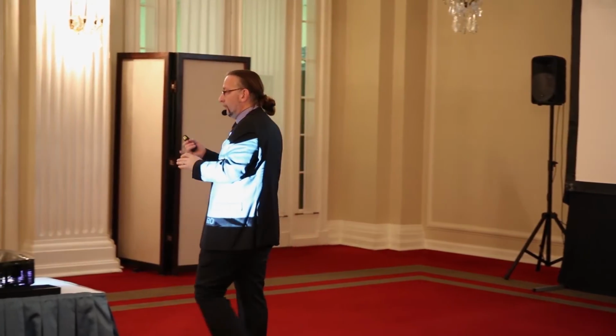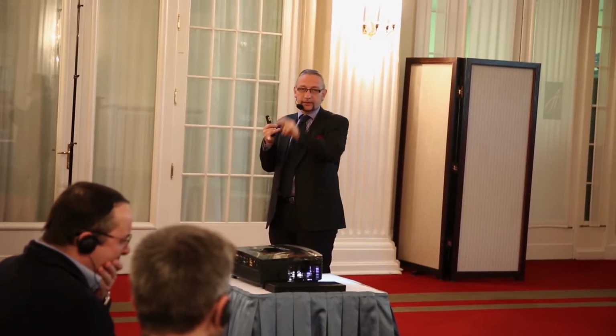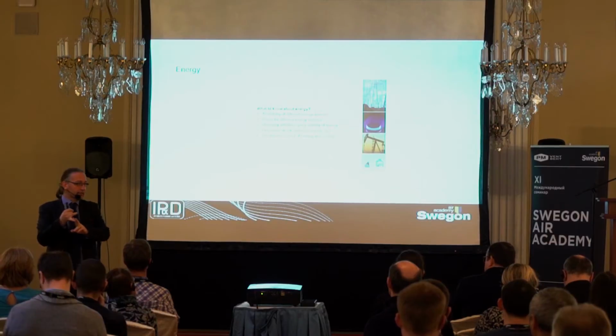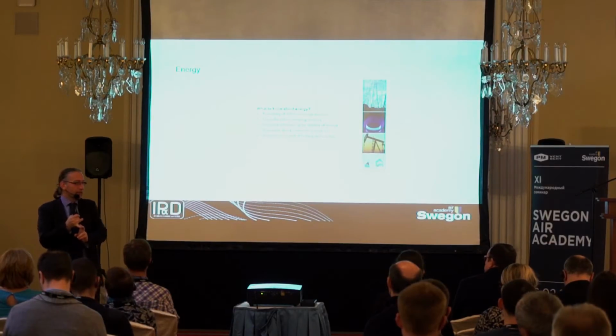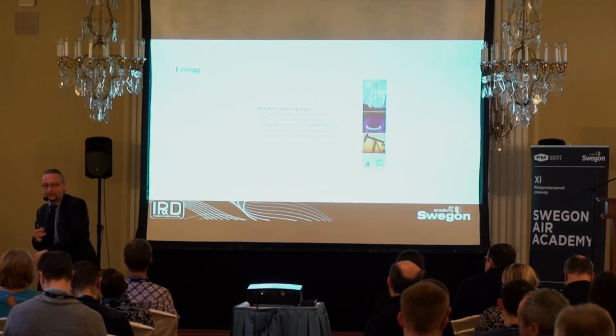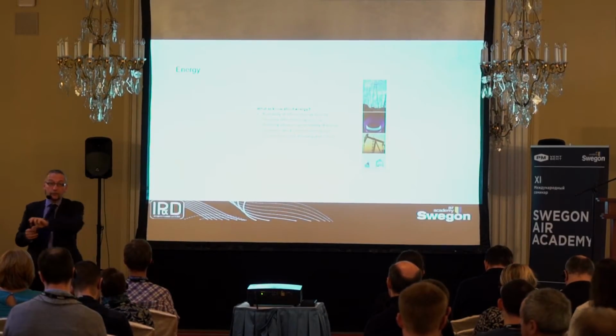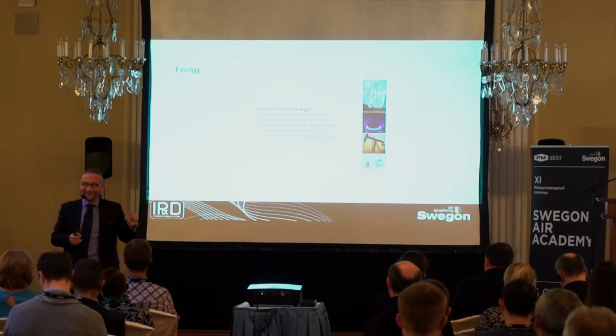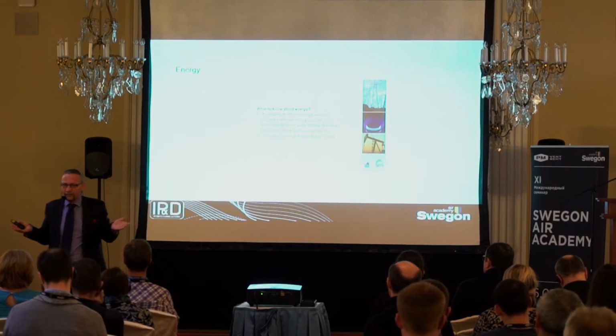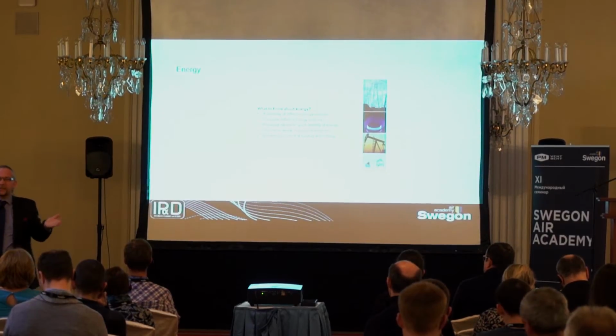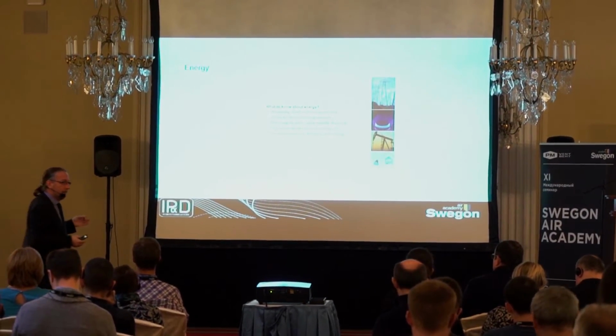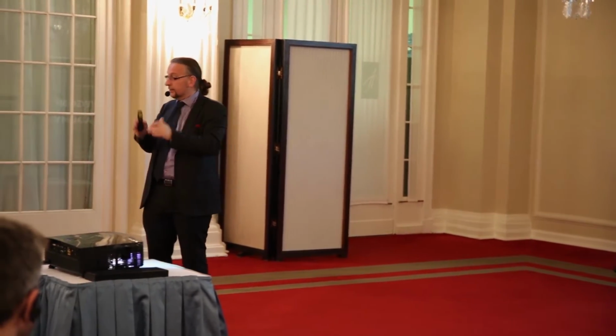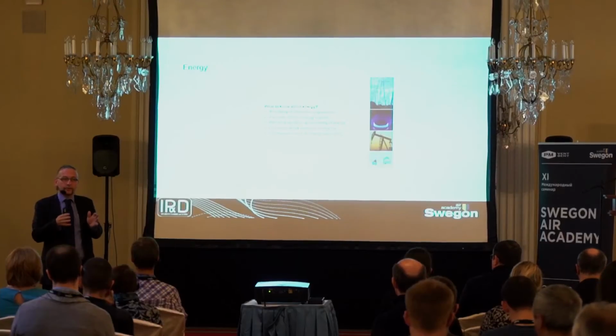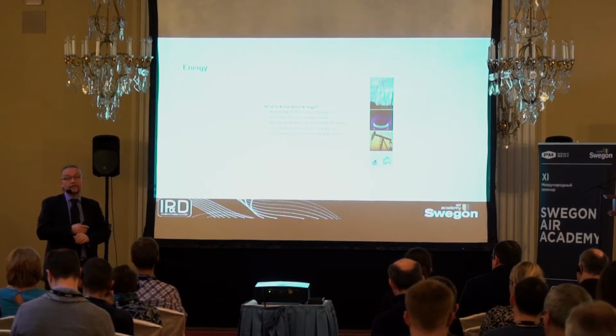So instead of paying for 100 kilowatt of heating and 100 kilowatt of cooling, you could only pay the electricity for the cooling, which is a COP of 3, so it's only 1/3, and you get all the heating for free. So directly your energy bill goes down by 70%. But still, it will need 2 more copper pipes. Yes, of course, they cost money. How much is that? 1 month of energy use in your building? It's nothing. So there's a lot of things you can do today to reduce your energy cost in existing buildings dramatically without too big of an investment or without inventing the wheel one more time.